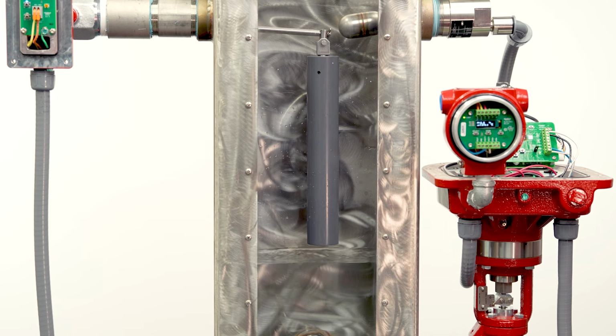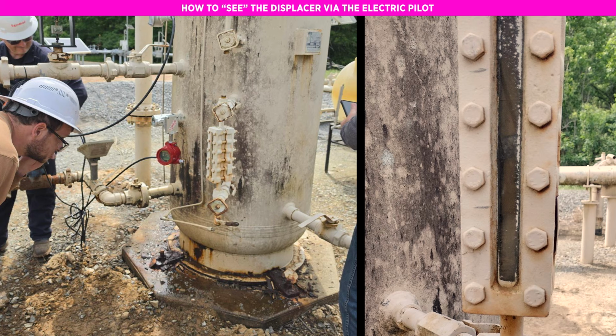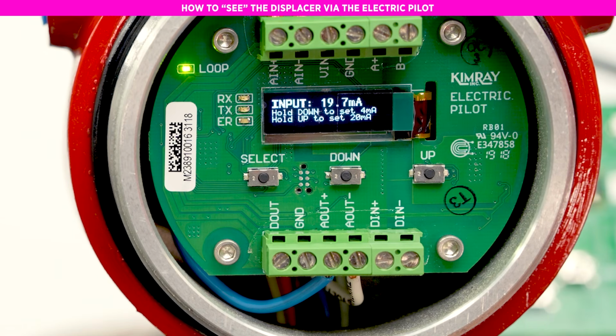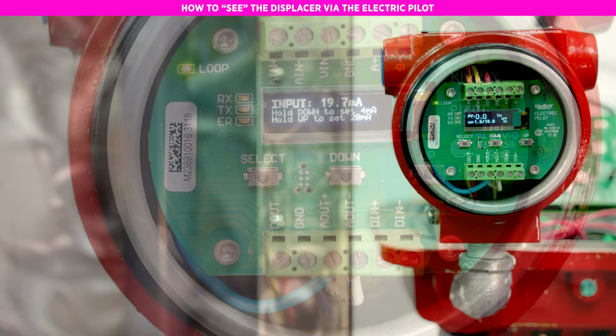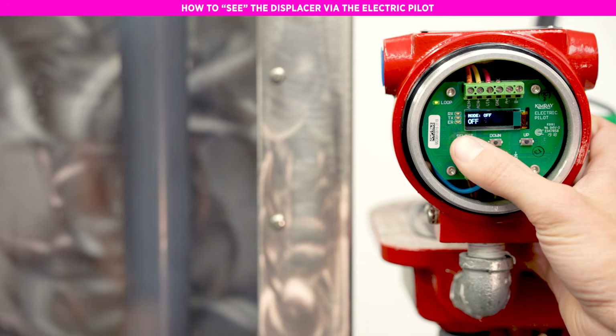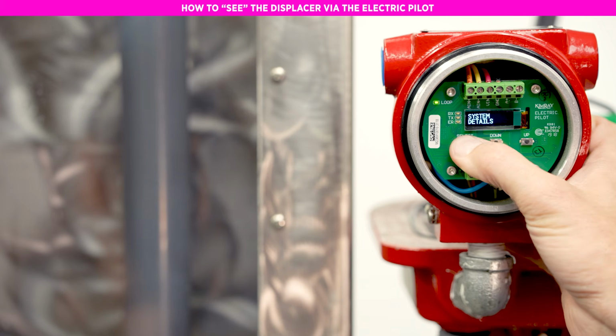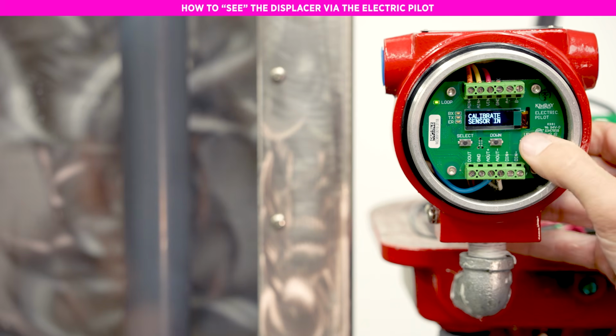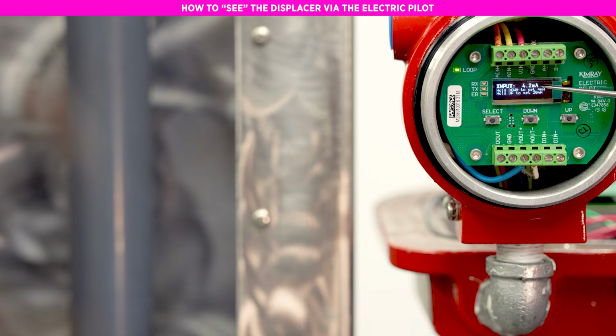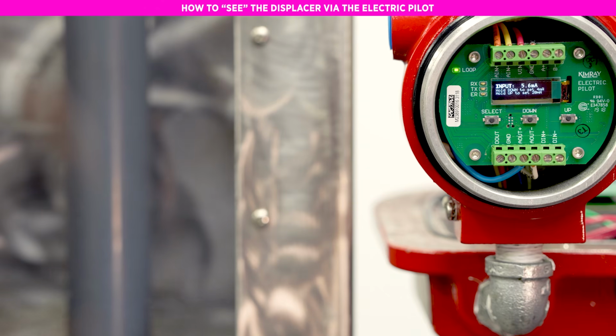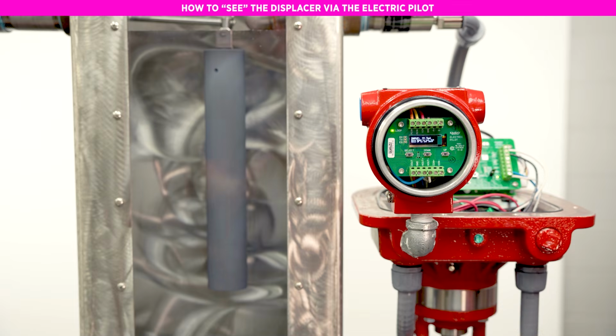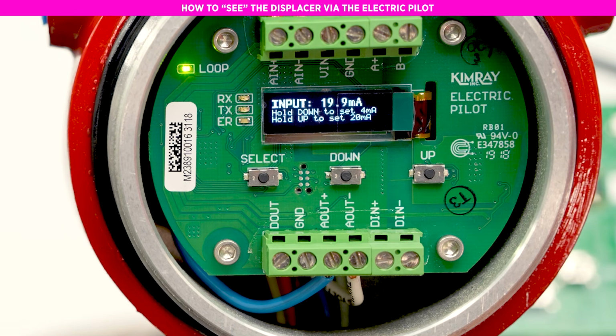It is easy to see our displacer in this demo unit, but in real-life scenarios, there are a couple ways you could do this accurately. You could use a sight glass, but it's not always the most reliable. The most precise way is to use the readout on the electric pilot or your PLC. To see the true position of the liquid level on the pilot, go to Advanced Settings, then Calibrate Sensor In to see the level sensor output. 4 milliamps means the level is below the displacer, and 20 milliamps means it's above the displacer. There's a small amount of deadband, so plus or minus a few tenths of a milliamp is normal, so it may hold around 19.8.